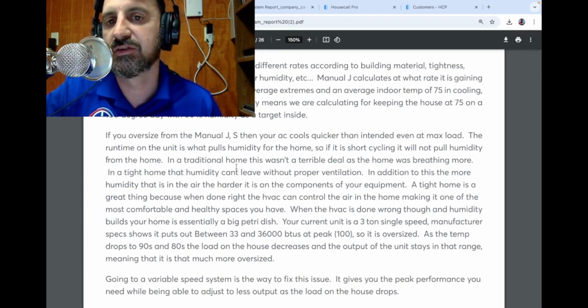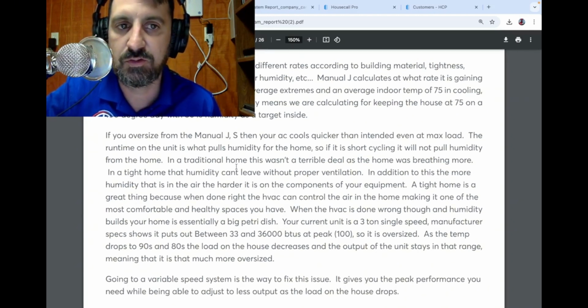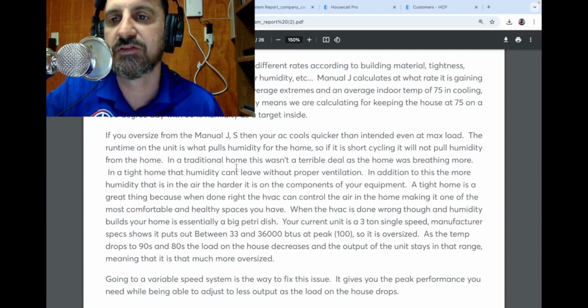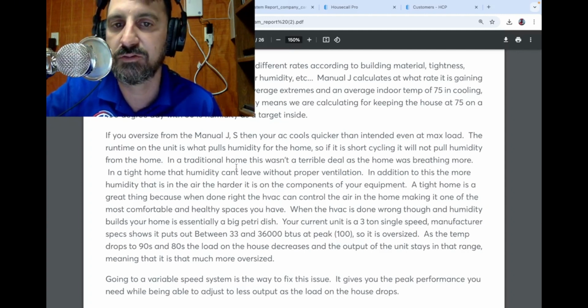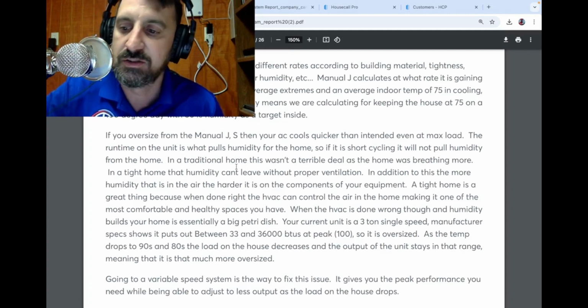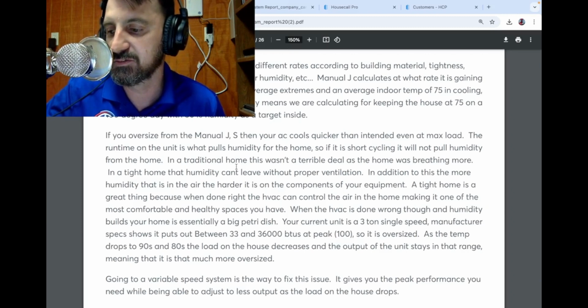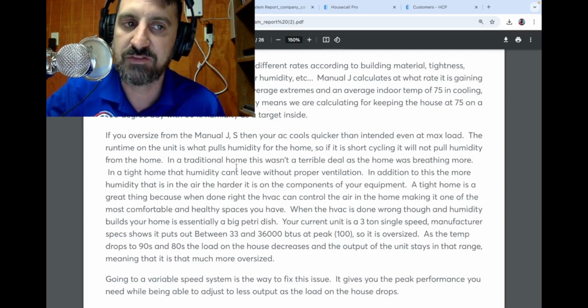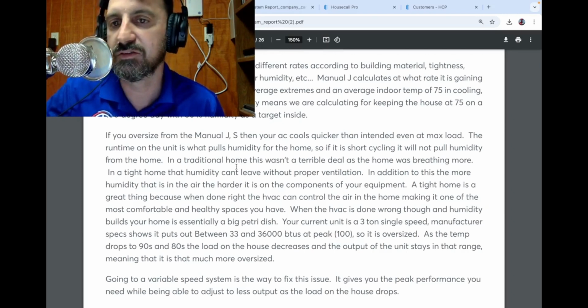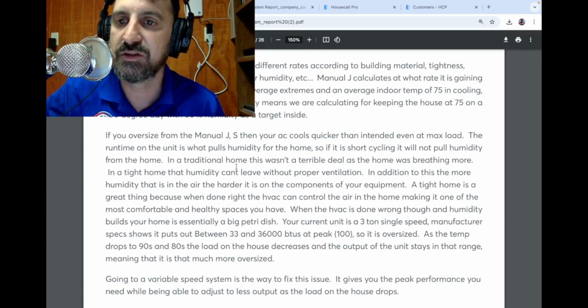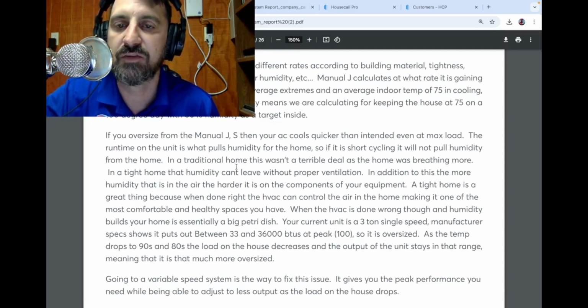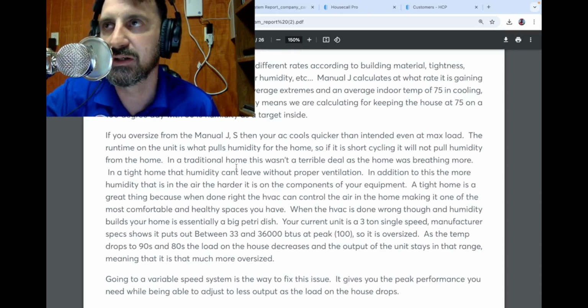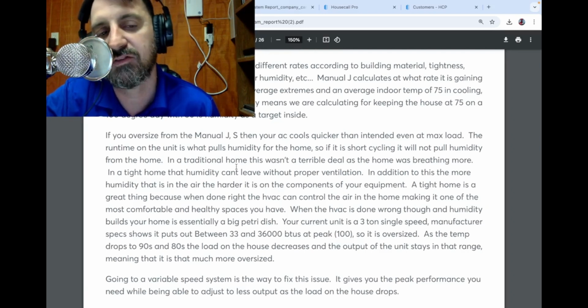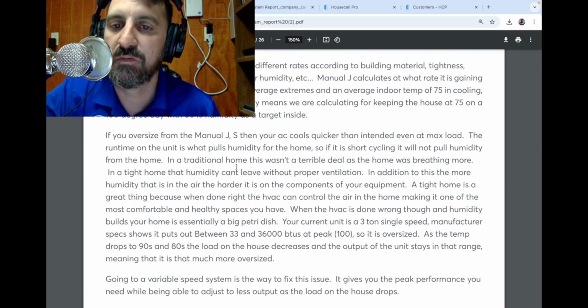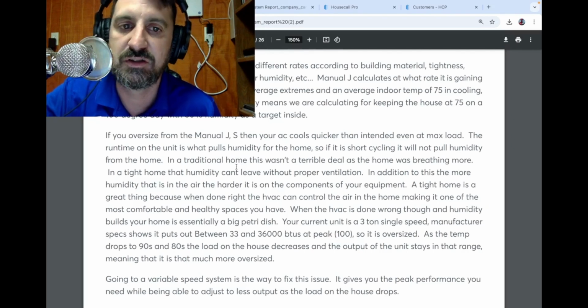Essentially, the house is gaining heat at different rates according to the building material, the tightness, the insulation, the outdoor temp, outdoor humidity, etc. Your Manual J calculation is your contractor taking all of that stuff into account when determining how many BTUs they need in this home. You put in kitchen equipment, washer and dryer, refrigerators, all of this stuff that creates heat, the number of people, the type of ventilation you need, etc.